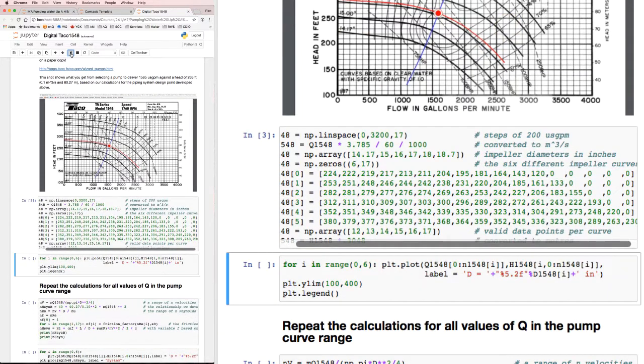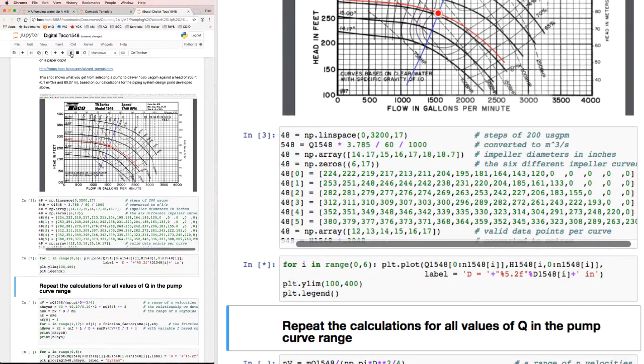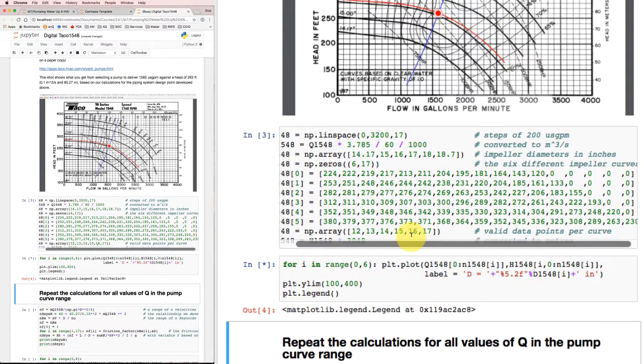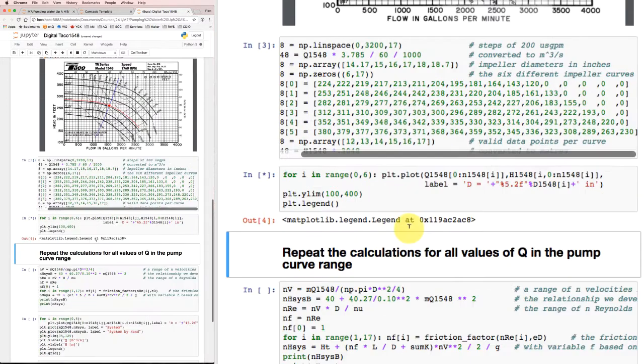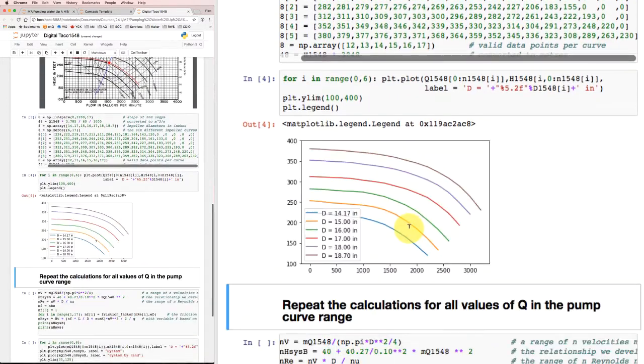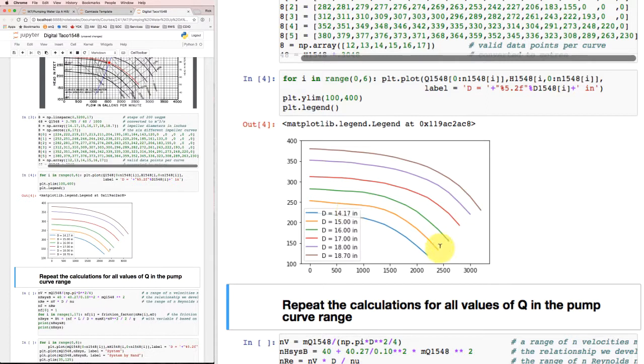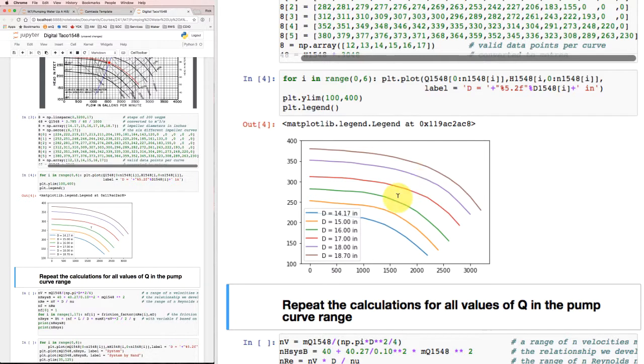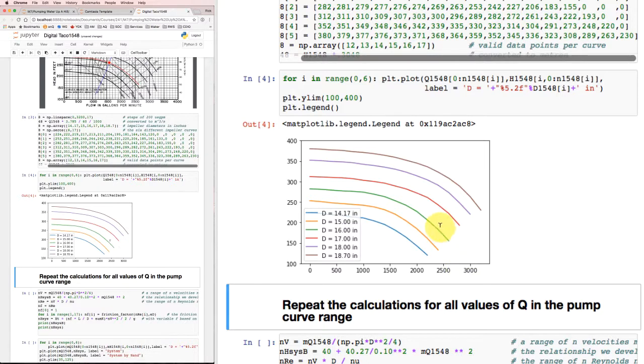So if we load that in, we can then plot that data out, and there are the curves that we got before. So we've got a reasonable representation of what the actual pump performance is in digital form. Now we've got to go and find out what is the system performance, the piping performance, over this whole range of flow rates based on our input from our piping system.